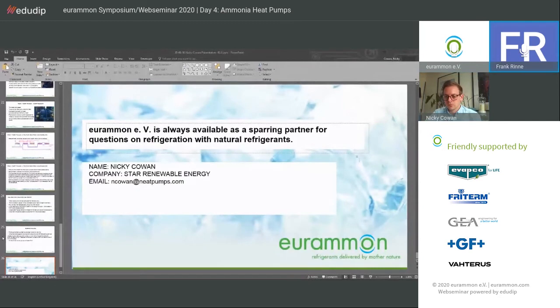There's another question from Adam Strachan. He's asking, is the self-cleaning process on the intake screen continuous, or is it on a time-based basis? So on a timed basis. I think the default for these systems is every 20 minutes, but it comes with its own controller and you can set it to whenever you need. So if you're super concerned, every couple of minutes, but you can make it longer as well. And it doesn't interrupt the process. So it's real-time cleaning.